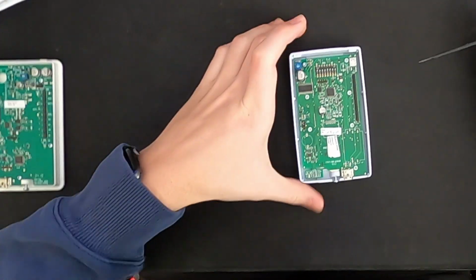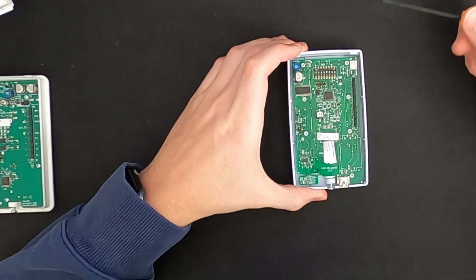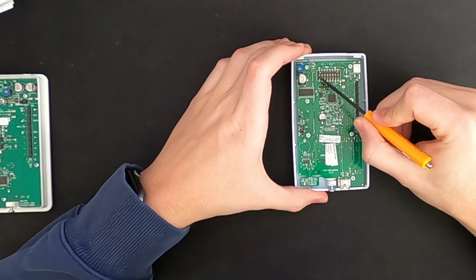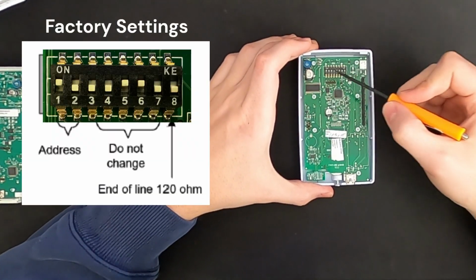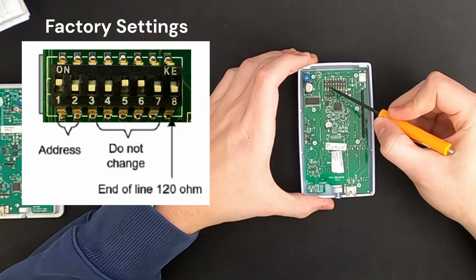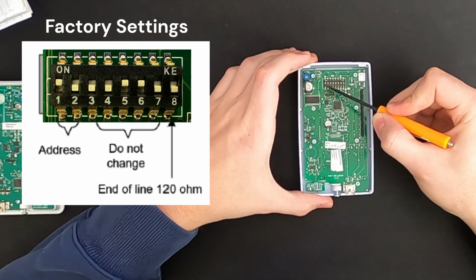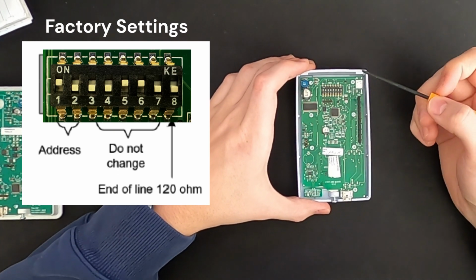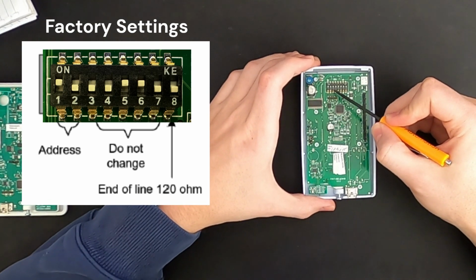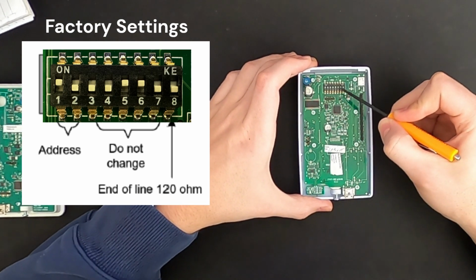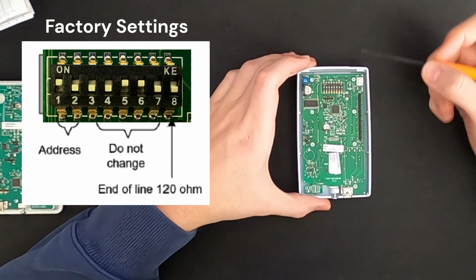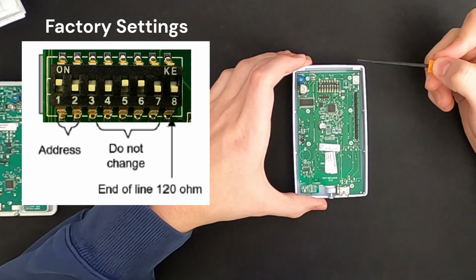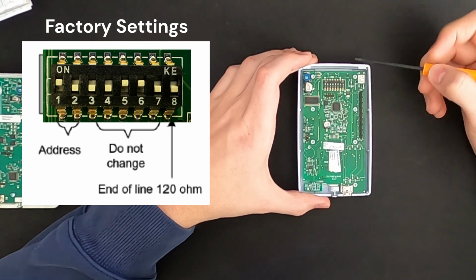So to start, we'll go with the TZ100 here. On the back, you have your dip switches. These first two are going to handle your addressing, so that's how you'll set it to either 1, 2, or 3. These middle ones, 3, 4, 5, 6, and 7, are unused. And then 8 is going to be your end of line, so whatever your last one is, you'll change that.